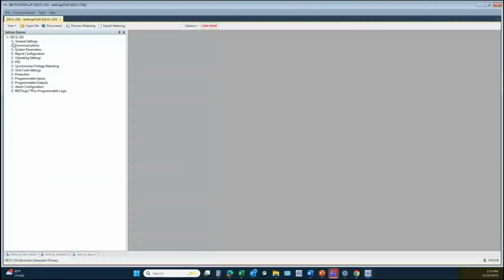I also want to note, whenever you use the software and you plan to use it for the same purpose, for example, commissioning the DECS 250, maybe you plan to commission DECS 250s on a regular basis, and there are certain screens that you always want to see come up. You can actually set up the software and open the various screens and then save that configuration, both the metering screens and the settings screens, in what's called a workspace file. So if we save that as a workspace, then you can reopen it later, and it will repopulate the software with the way you had left it.